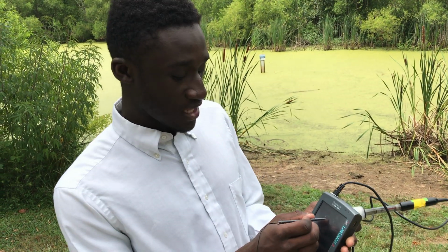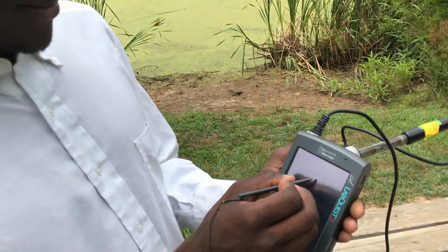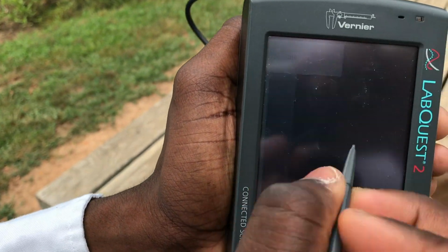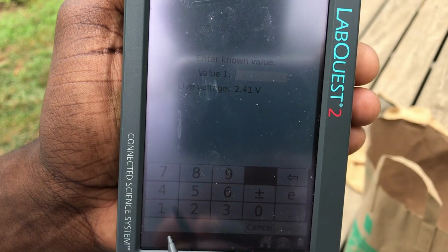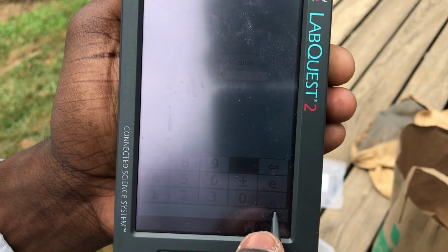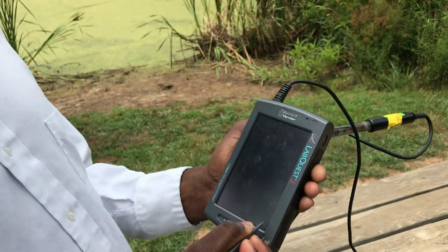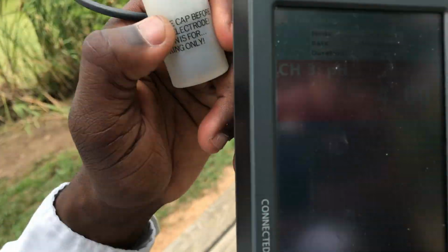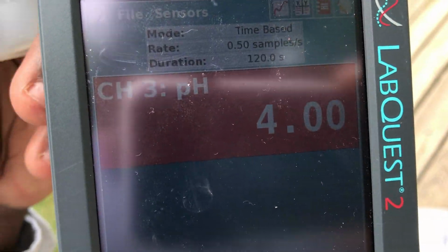Now we're going to click Calibrate Now. There we go. I clicked OK. Calibrate Now, and enter the known value. We know the known value of this should be 4, and our units were already placed in pH. If your units weren't in pH, you might want to check that. Keep. OK. Now we're done. Now it's going to stay at a consistent 4, and we know that this solution is 4 for our pH, and we can accurately test our water.